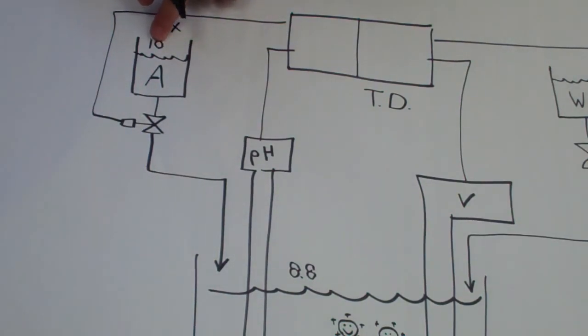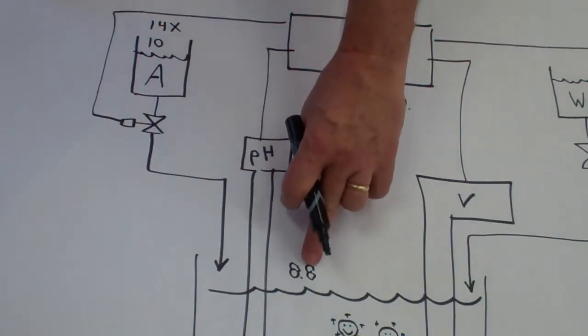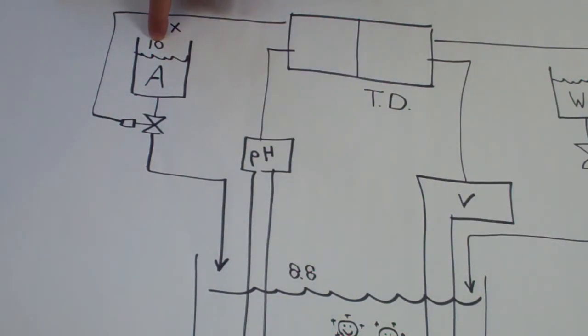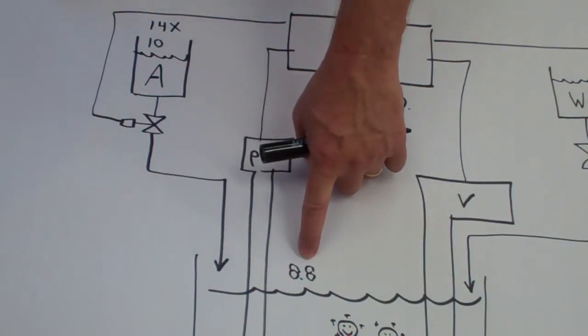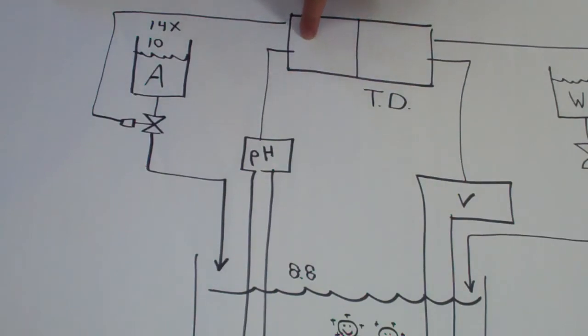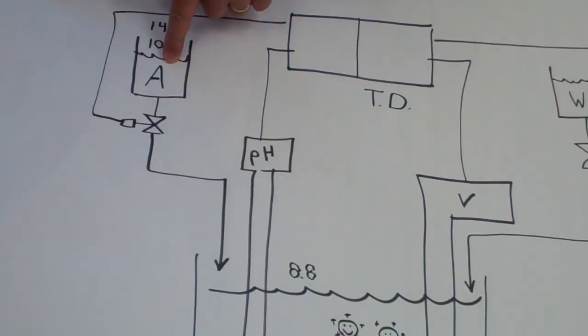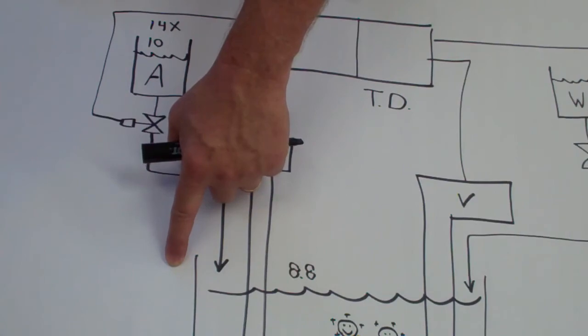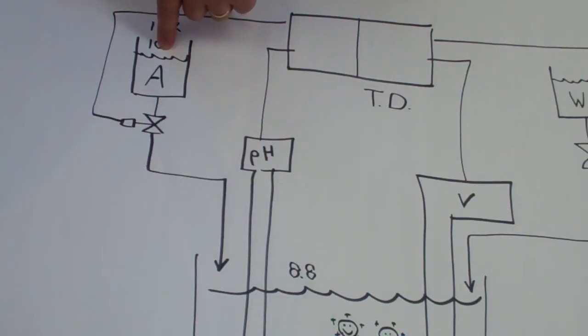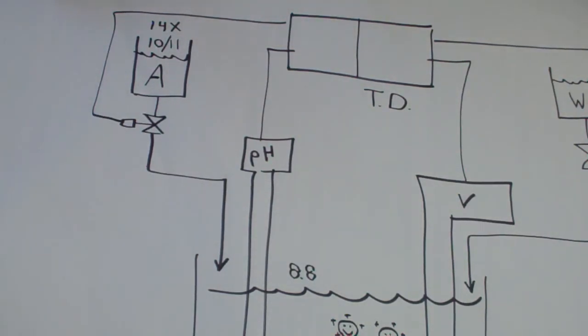This pH should be 1, 2, maybe 2 or 3 points above this value. If this was 9.0 and you're controlling at 8.8, the pH control loop will add so much of this amine solution, which does contain water, that you'll end up filling up the bucket full of ink and probably spilling it over. Because to get, if this is a 9 and you're at 8.8, to bring it up, you have to add a lot of material. So you want a decent differential here, not an extreme differential. This could be 10, it could be 11, in that range.